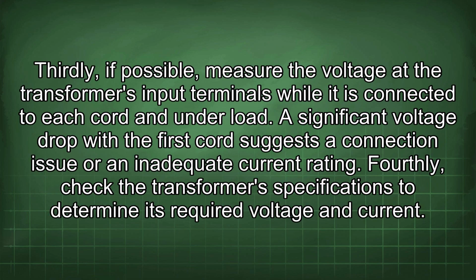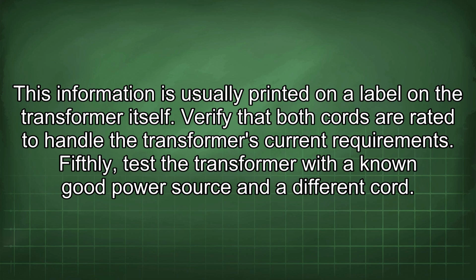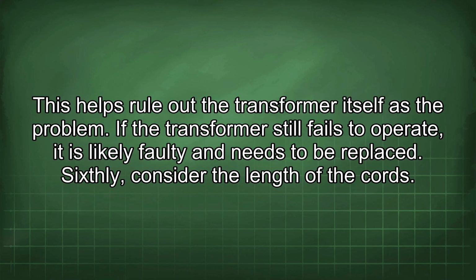Thirdly, if possible, measure the voltage at the transformer's input terminals while it is connected to each cord and under load. A significant voltage drop with the first cord suggests a connection issue or an inadequate current rating. Fourthly, check the transformer's specifications to determine its required voltage and current. This information is usually printed on a label on the transformer itself. Verify that both cords are rated to handle the transformer's current requirements. Fifthly, test the transformer with a known good power source and a different cord. This helps rule out the transformer itself as the problem. If the transformer still fails to operate, it is likely faulty and needs to be replaced.